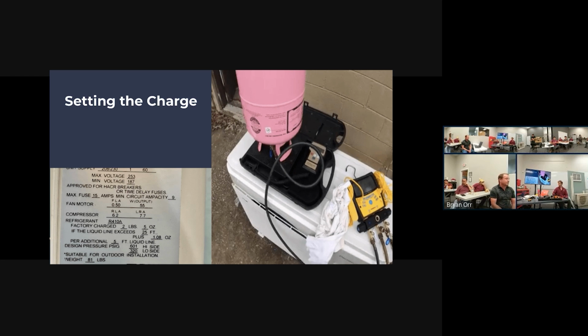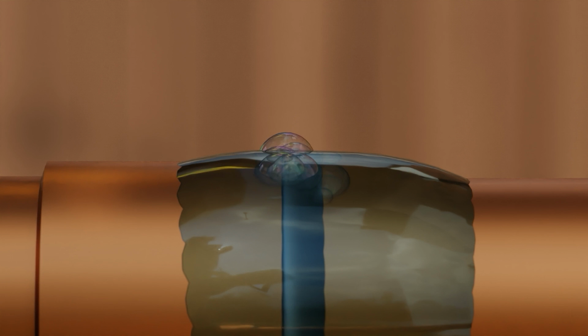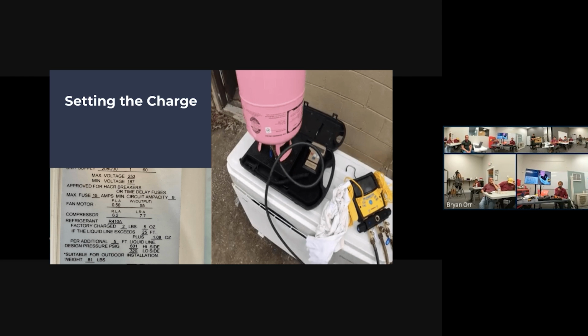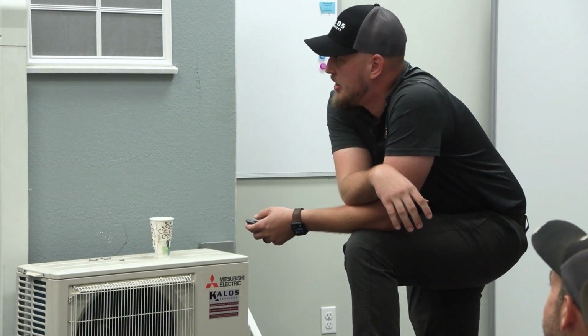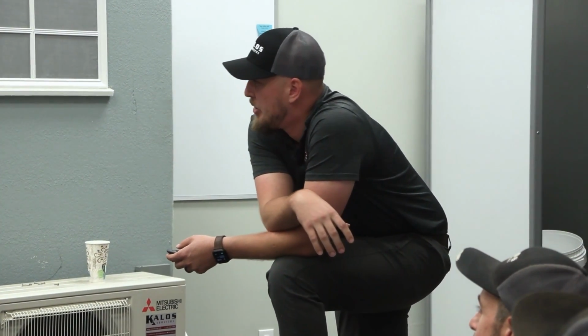Another thing that I want to mention with bubble testing, Bert talks about this a lot in other videos. When you are spraying bubbles on, you don't want to just spray willy-nilly and create a bunch of foam that then makes it difficult to tell if you have leaks. You want to put it on very flat and then actually let it sit and look for those little micro bubbles, especially on flares. On flares, really pay attention to your flares. Make sure that we don't have even tiny leaks with flares.